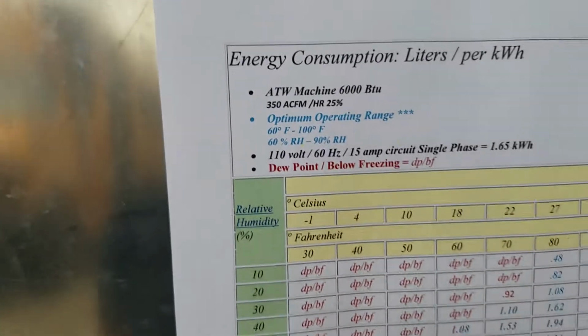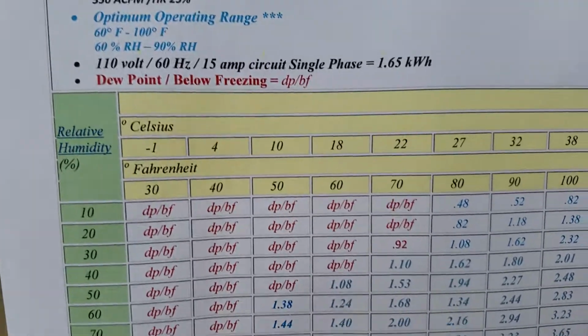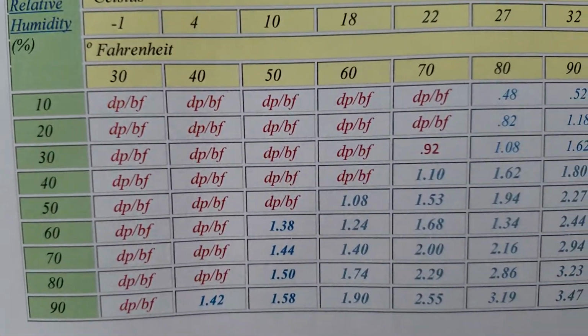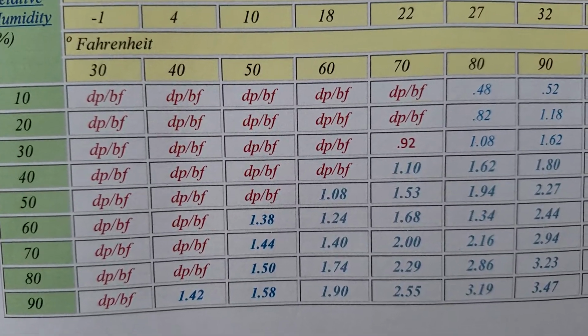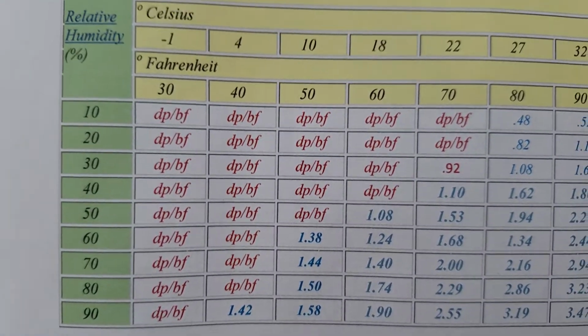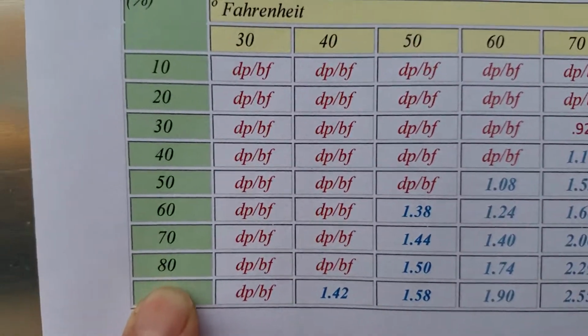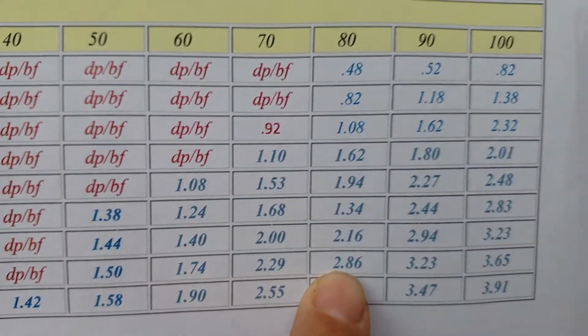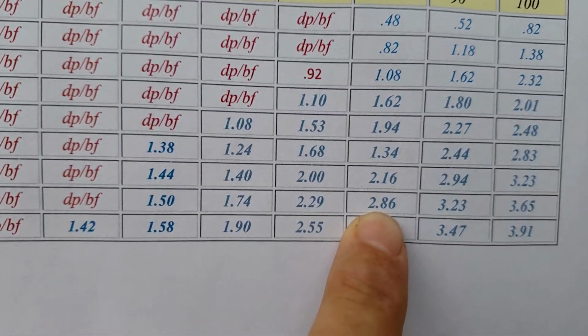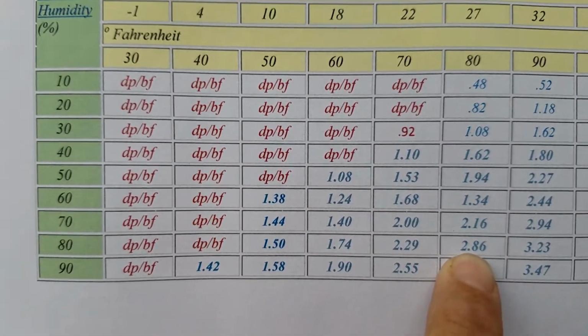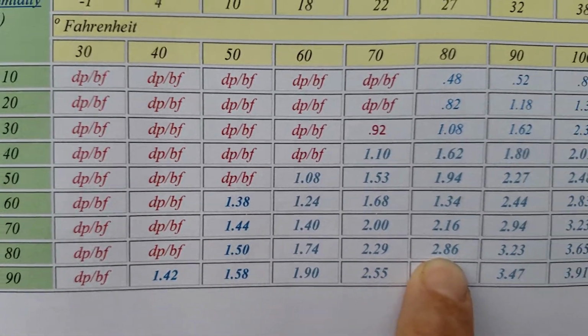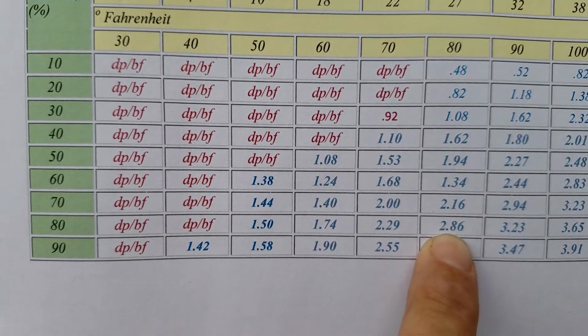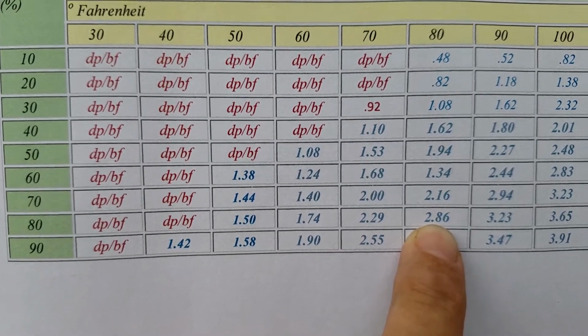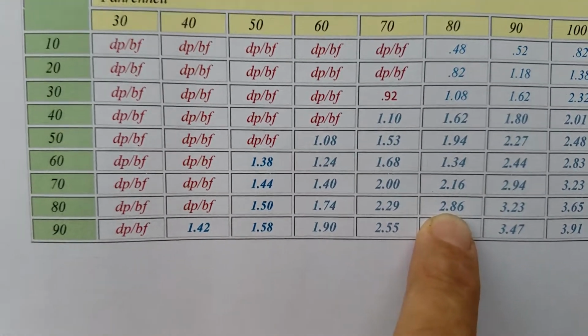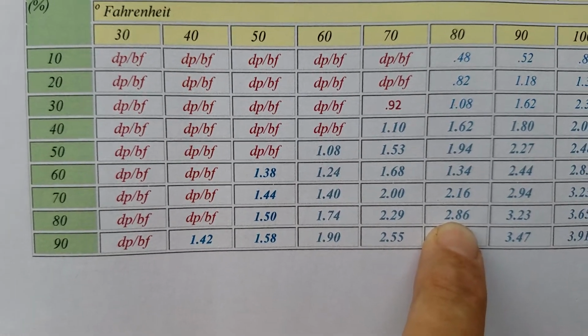So our next chart is the liters per kilowatt. And so it seems that we're using the 80 by 80 as a typical refrigeration heat load, or excuse me, air conditioning heat load. We'll do the same. We'll come down here to 80% relative humidity, and we'll go across the chart to 80 degrees. And at 80 by 80, this generates 2.86 liters per kilowatt. Now, the average kilowatt cost in the United States is 12 cents per kilowatt. So essentially, we're getting 2.86 liters for 12 cents.